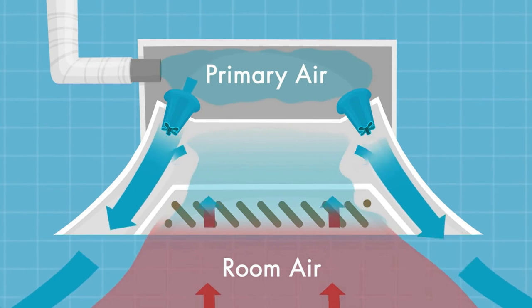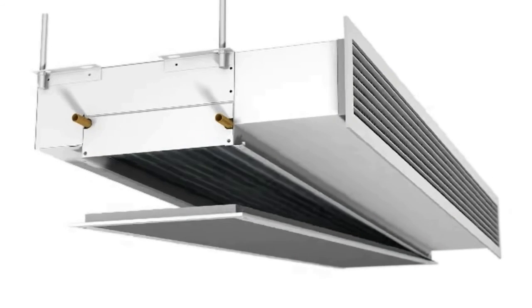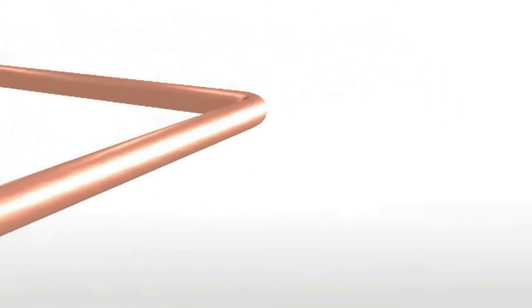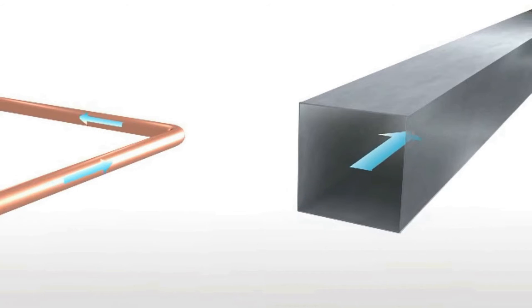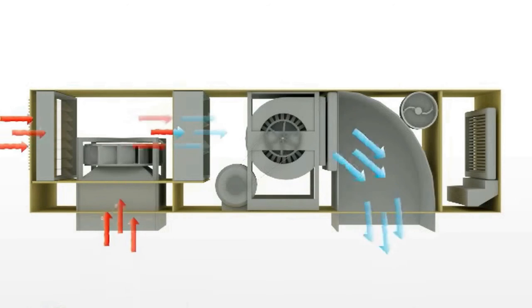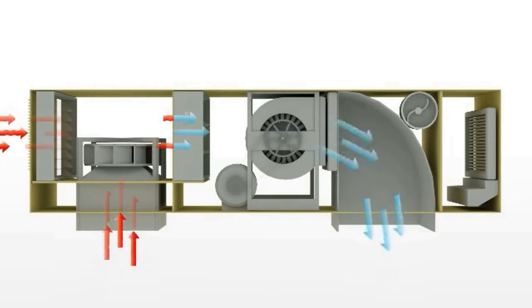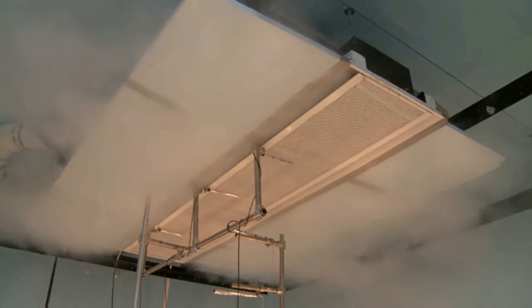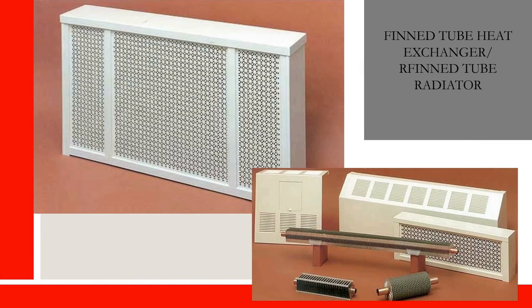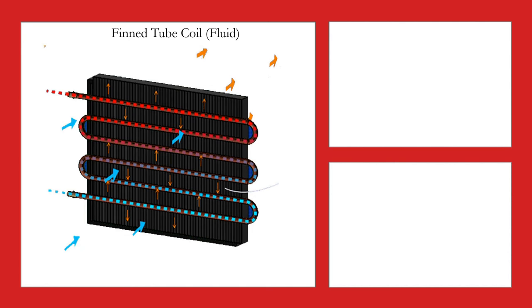This system can be both passive, utilizing natural phenomena like convection, or active by using fast-moving ventilated air entering to induce circulation of air out of the unit. The beam can also be used to radiate heat outwards during cooler months of the season. Another system integrated into New Balance's headquarters is the fin tube radiator. These also act similarly to chilled beams as a heat exchanger via convection in the offices.